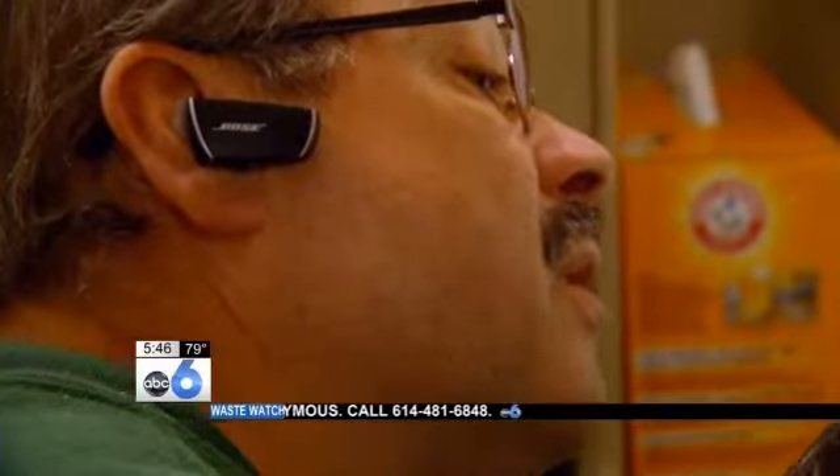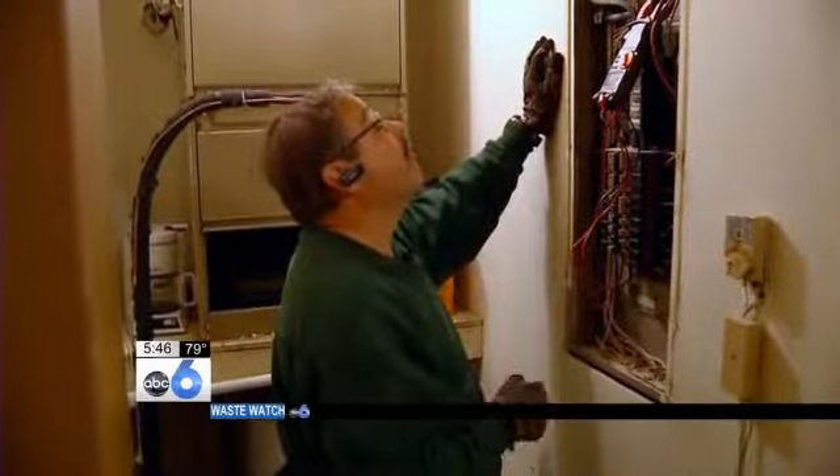So we called our own electrician. David Diehl is with DA Electrical. Checking the panel inside, Diehl first looks at the power load with everything turned off — reading less than an amp on the whole service. Then again with everything turned back on: about 37 amps.